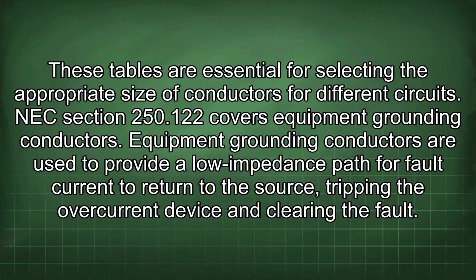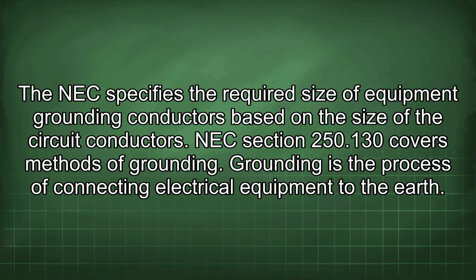NEC Section 250.122 covers equipment grounding conductors. Equipment grounding conductors are used to provide a low impedance path for fault current to return to the source, tripping the overcurrent device and clearing the fault. The NEC specifies the required size of equipment grounding conductors based on the size of the circuit conductors.